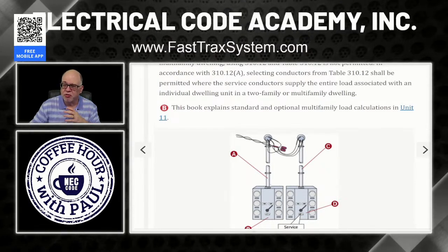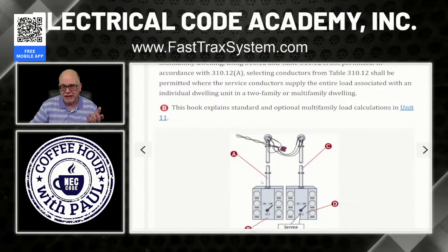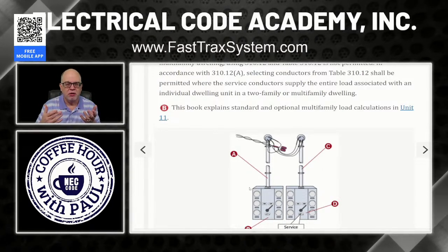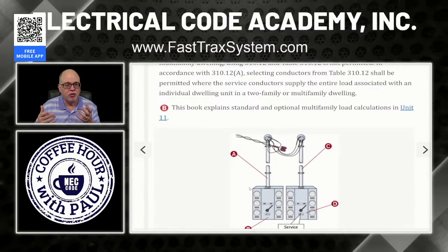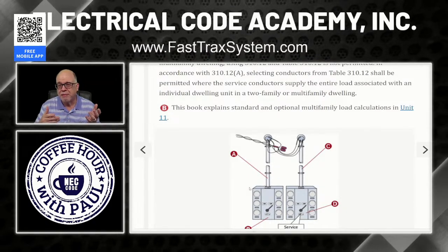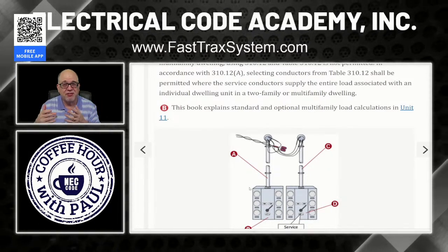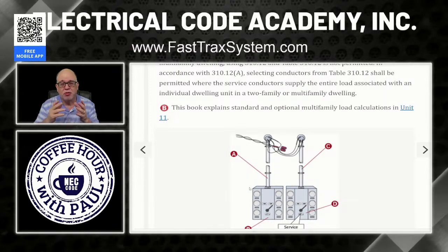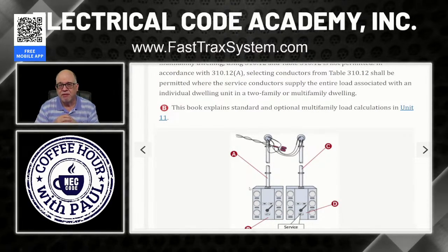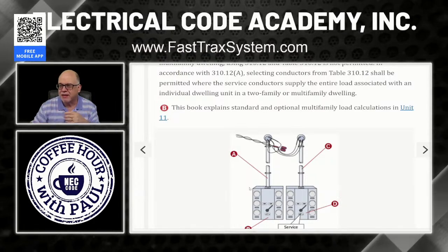Also, since this is supplying six units, it's not supplying a one-family dwelling or an individual dwelling unit. That's also something 310.12 tells you: unless you're doing that, you can't use the 83% rule. So what does that mean? Well, that means you have to size the conductors using the normal ampacity table, 310.16. Okay? You don't get to use the 83% rule. You just size them like you normally would, using the ampacity values from the normal ampacity table 310.16. Hopefully I made that clear for you.